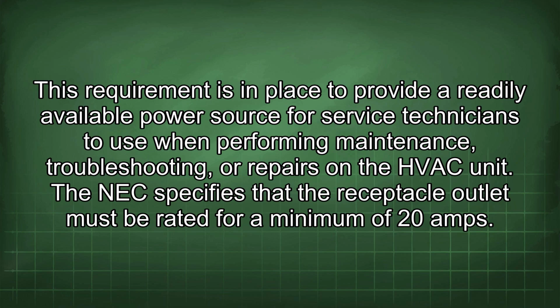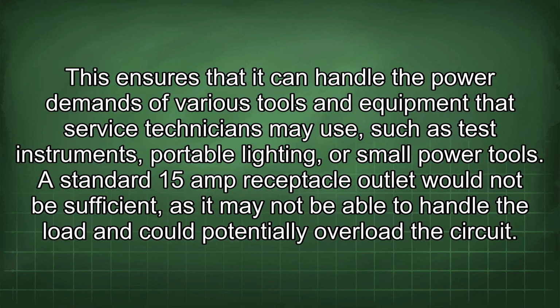The NEC specifies that the receptacle outlet must be rated for a minimum of 20 amps. This ensures that it can handle the power demands of various tools and equipment that service technicians may use, such as test instruments, portable lighting, or small power tools. A standard 15-amp receptacle outlet would not be sufficient, as it may not be able to handle the load and could potentially overload the circuit.